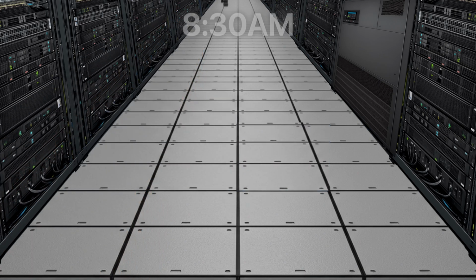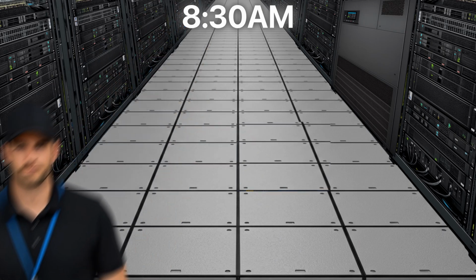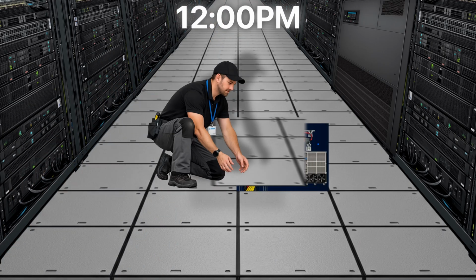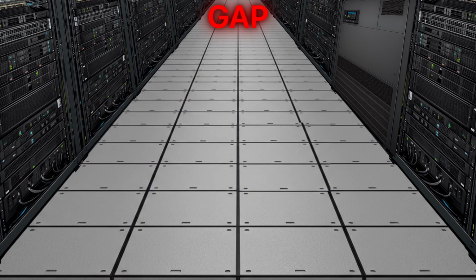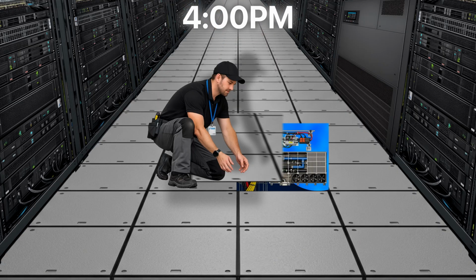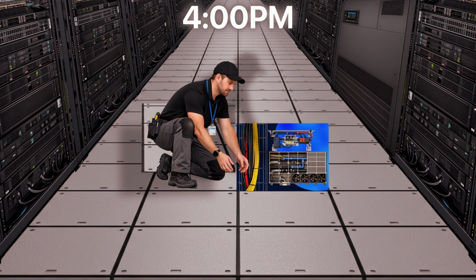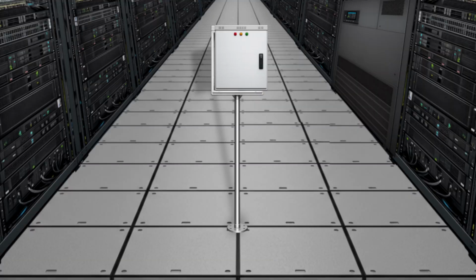The industry standard response to this has historically been periodic visual inspection. This means your detection window is whatever gap exists between your last walkthrough and your next one. In a live production environment, that gap is where the damage actually happens. What you actually need is continuous monitoring that covers the floor space where water would collect. That tells you the moment something changes, not the next time someone happens to walk by.